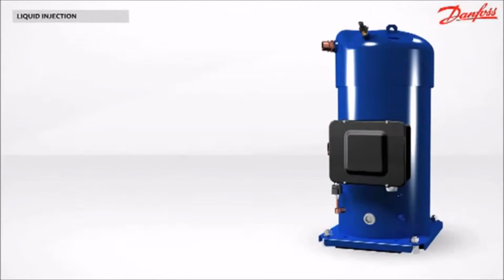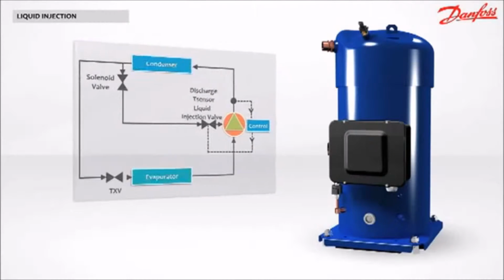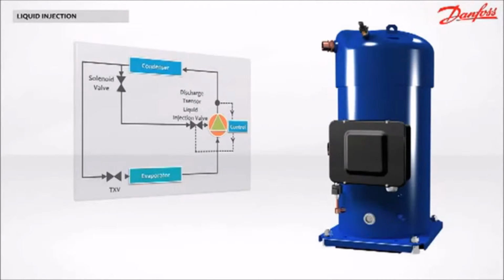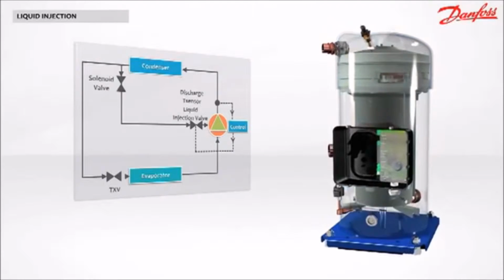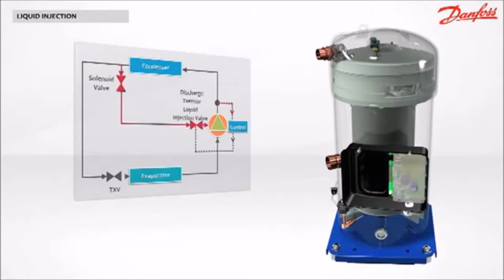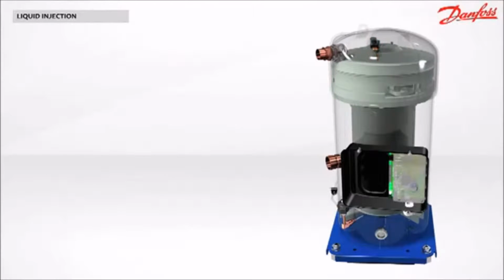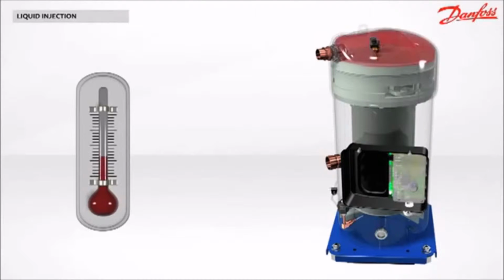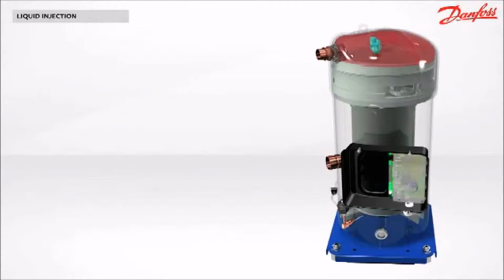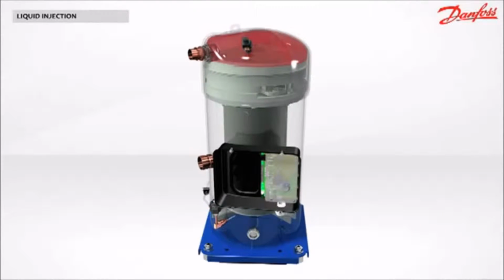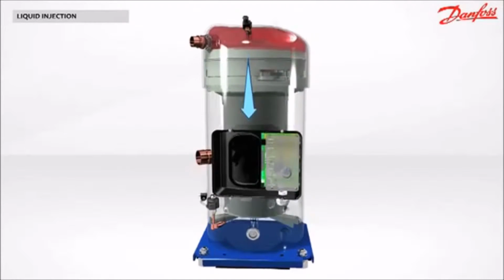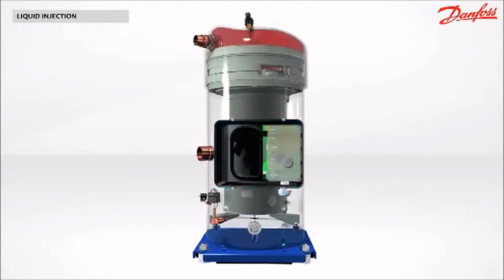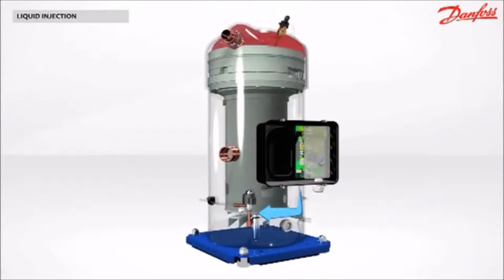Liquid injection, how does it work? Here you see a basic vapor compression cycle sketch. Some of the liquid leaving the condenser is used to cool down the discharge gas. When the discharge temperature reaches the limit, the discharge gas temperature sensor sends the information to the operating control system located in the electrical box. This control system pilots the opening of the electronic expansion valve.